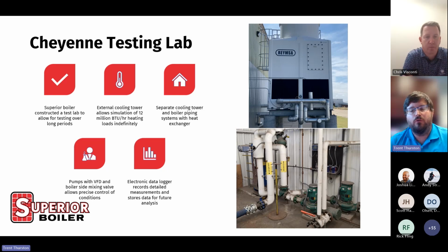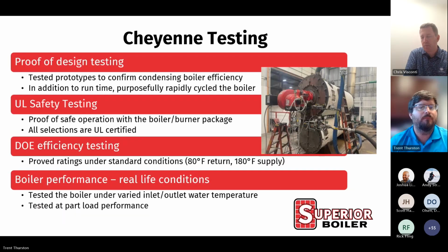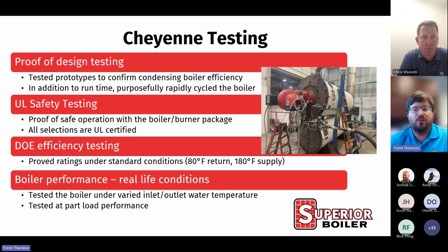VFDs and mixing valves coming out of the heat exchanger allowed us to set the supply temperature, return temperature, and flow rate through it. And then we had an electronic data logger, which would measure gas flow, water temperatures, and flue gas temperatures, and allows us to monitor this at a later time. So in our testing phase, again started in 2020, we first tested the longevity and efficiency of the boiler and proved our design that way.